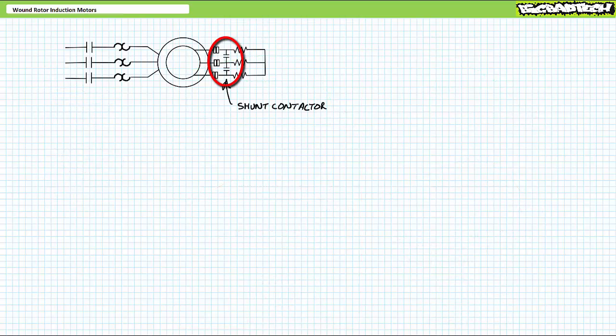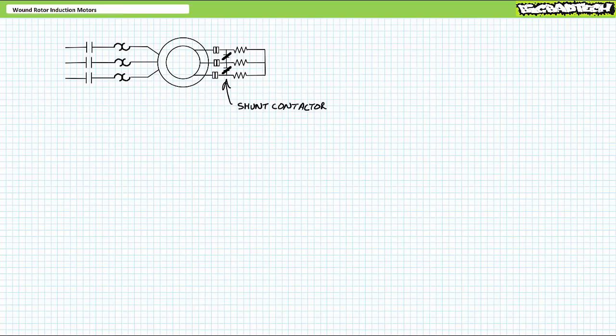One way of toggling between D and B operation is with a shunt contactor in parallel with a rotor resistance bank. When the shunt contactor is open, the external resistor bank is placed in series with the rotor and the motor operates like a high resistance design D squirrel cage induction motor. In contrast, when the shunt contactor closes, the resistor bank is shorted out or bypassed, excluding them from the rotor circuit, and the motor operates like a low resistance design B squirrel cage induction motor.